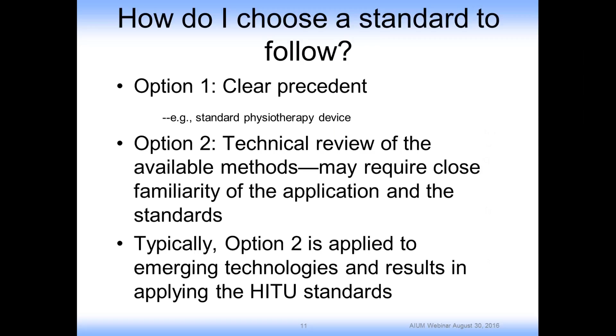The first is concern that high intensities or pressures could damage hydrophones. Although research is continuing on robust hydrophones that would not have this problem or would alleviate this concern, still none are completely impervious to the levels that could be achieved by some therapeutic ultrasound. Therefore, and also even more importantly, it's very hard to define definitive thresholds for when you should or shouldn't use a hydrophone. So therefore, measurements at these high pressures will take more guidance about how to check for applicability and also how to check for damage. That's under development, but it's not yet released as a standard. So therefore, the current standards had to deal with this as an issue.